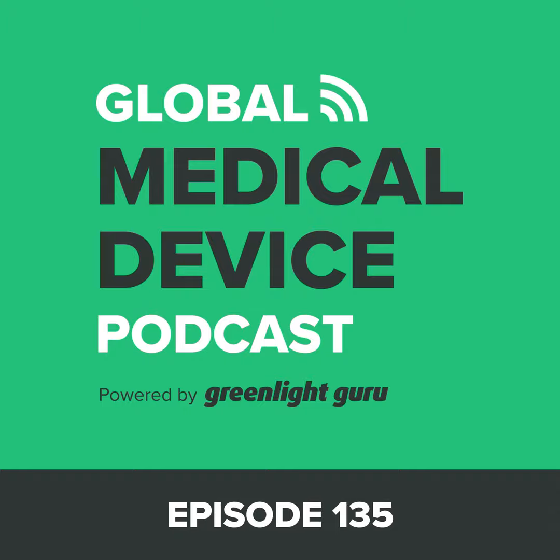The manufacturer proceeds at their own pace. And when you've completed everything that you say you will complete, then FDA essentially approves your device as a Class 3 device. So this product development protocol, as I said, is extraordinarily uncommonly used. But in the spirit of medical device professionals, especially regulatory professionals, knowing all their options, if they're a regulatory professional and they don't know what the PDP is, then in my book, John, they're not a regulatory professional. A couple of other pathway options to be aware of: the humanitarian device exemption, or the HDE. This is also at the top of the medical device pyramid.